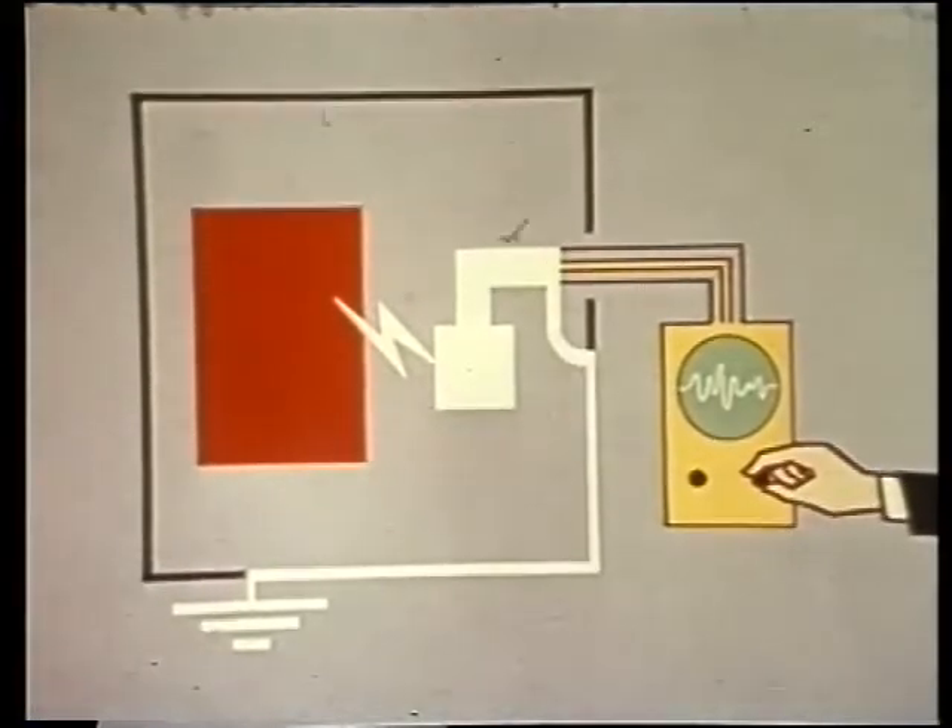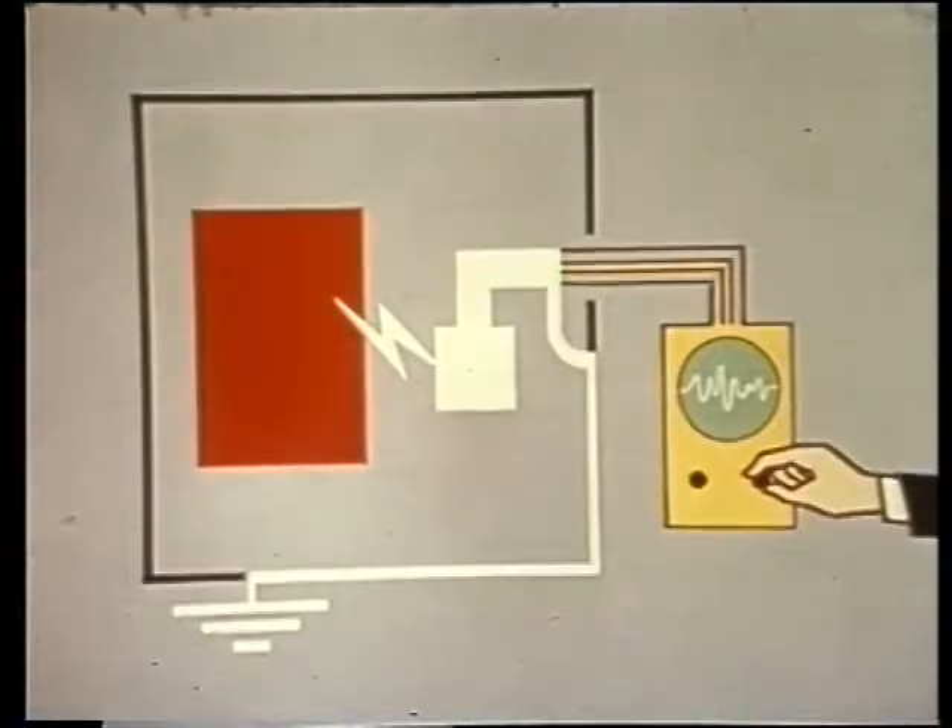The leads make a breach in the safety barrier, and diagnostic currents pass along them. But if insulation breaks down inside the cage, high voltages will escape along the leads too. So the answer is to cage the diagnostic leads as well — in other words, screen them and earth the screening. If high voltage is shorted across now, they'll go to earth direct and not through the man.